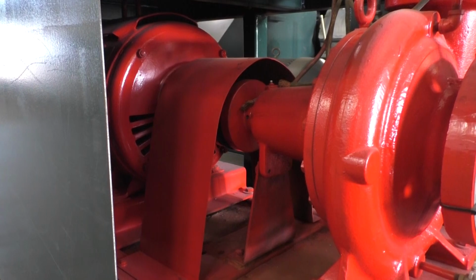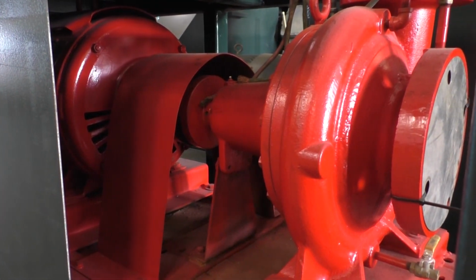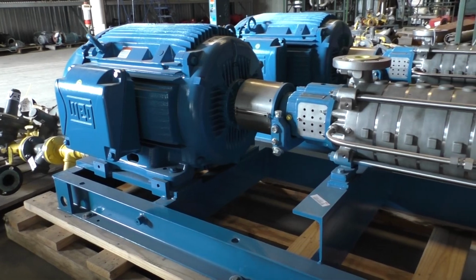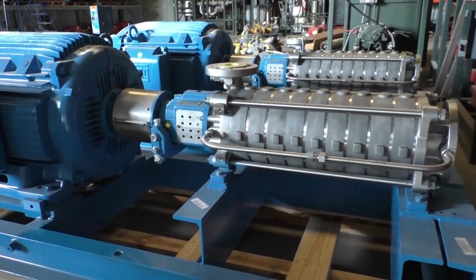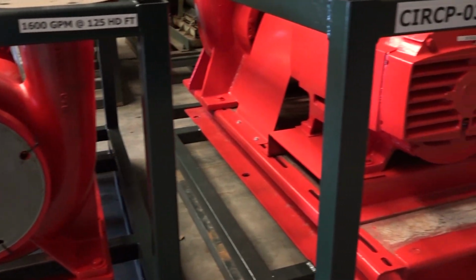So as previously discussed with regards to pump selection, feed pumps require careful consideration to ensure that the pump not only can overcome the boiler's pressure as well as maintain the flow requirements, it also must meet specific net positive suction head requirements. Wait, say what? So first, let's talk about why NPSH, or net positive suction head, even matters in a pump.